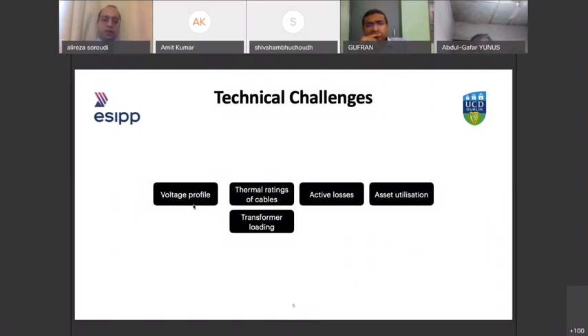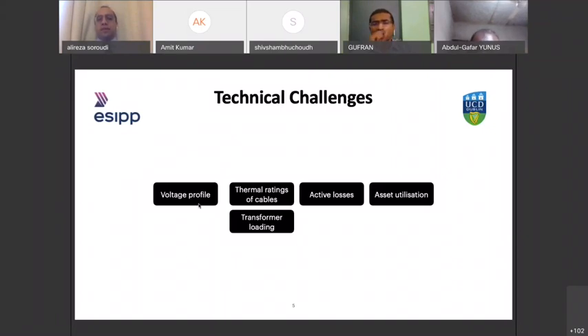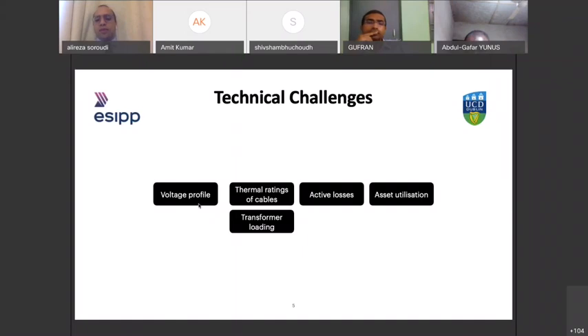One of the most important challenges is the voltage profile. When we have DG units in the system — for example PV or photovoltaic units — during a sunny day we might have voltage rise in the network, thermal rating of cables might be violated, and the transformer loading might be affected. The transformer is a very expensive asset, and the active losses in the network — which reflect the efficiency — will also be changed.